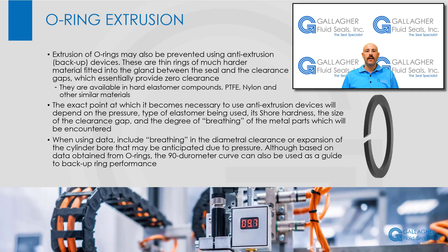Extrusion of O-rings may also be prevented by using anti-extrusion devices known as backup rings. These are thin rings of much harder material fitted into the gland between the seal and the clearance gaps, which essentially provide zero clearance. They are available in hard elastomer compounds, leather, PTFE, nylon, and other similar materials. The exact point at which it becomes necessary to use anti-extrusion devices will depend on the pressure, type of elastomer being used, its shore hardness, the size of the clearance gap, and the degree of breathing of the metal parts which will be encountered. When using the data, include in the diametrical clearance any breathing or expansion of the cylinder bore that may be anticipated due to pressure. Although based on data obtained from O-rings, the 90 durometer curve can also be used as a guide for backup ring performance.